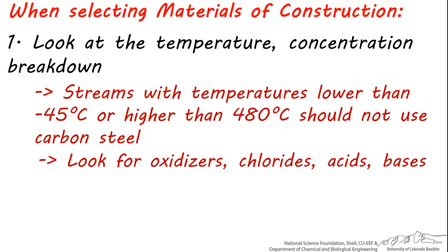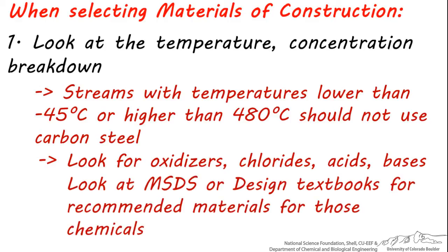Next, look for oxidizers, chlorides, acids, or bases in the stream going through the piece of equipment. If you see these or any other potentially corrosive or reactive chemicals at significant concentration levels, look in a design book or on a material safety data sheet to see which materials are recommended. Peters, Timmerhaus, and West, and other design books have chemical and material compatibility charts for many common chemicals. If you cannot find an exact chemical listed in a compatibility table, look for a chemical that's similar to it.